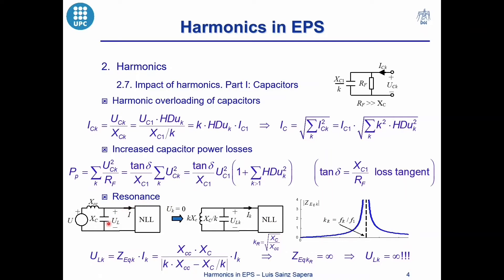Imagine that we have a capacitor bank to compensate the reactive power of an electrical installation and there is a non-linear load connected in this installation. If we want to calculate the harmonic voltage distortion at the non-linear load terminals by means of the approach presented in the videos about the resolution of harmonic problems, we must work with this harmonic equivalent circuit. The harmonic voltage is equal to the equivalent impedance of the parallel between the grid and the capacitor reactances multiplied by the harmonic currents consumed by the non-linear load. We can observe that for a certain harmonic the denominator of the equivalent impedance becomes zero, and then this equivalent impedance becomes infinite at that harmonic.